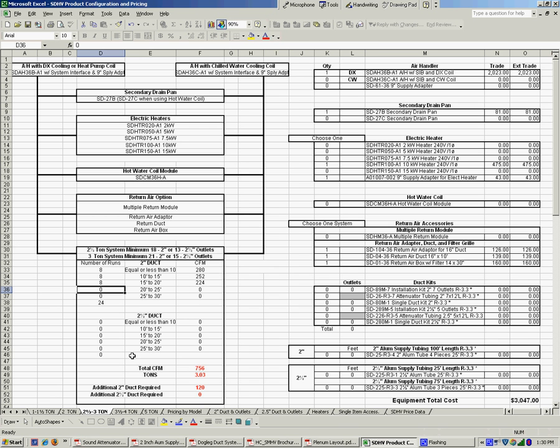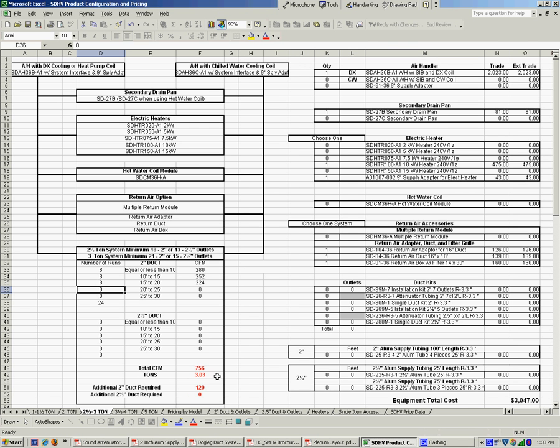Now what we've done here is we've said from that calculation, we're going to have a total CFM output of this system of 756 CFM, which is perfect. Remember, we're going to do 250 CFM per ton. That means we've got a cooling load on this system at 3.03 tons, it's an ideal situation. We need 24 outlets.